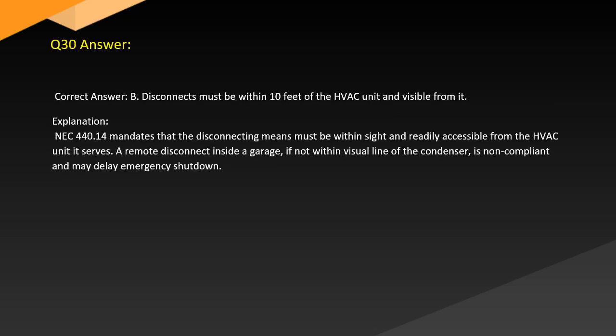Answer. Correct answer: B. Disconnects must be within 10 feet of the HVAC unit and visible from it. Explanation. NEC 440.14 mandates that the disconnecting means must be within sight and readily accessible from the HVAC unit it serves. A remote disconnect inside a garage, if not within visual line of the condenser, is non-compliant and may delay emergency shutdown.